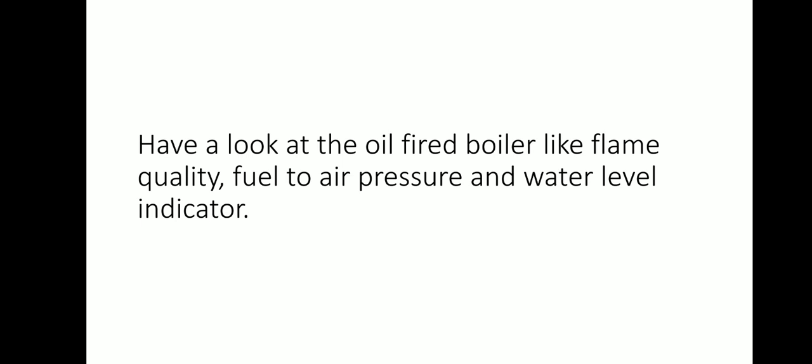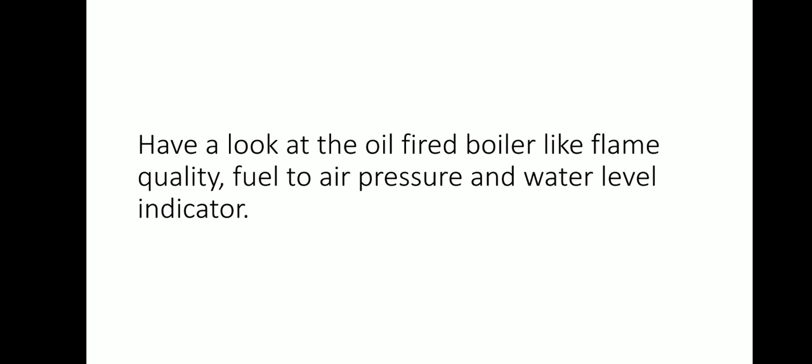We also have to look at the oil fired boiler — mainly the flame quality, then the fuel to air pressure ratio, the water level indicator, and from the control panel, check all indicators and gauges to understand the current condition, whether it is good or not.